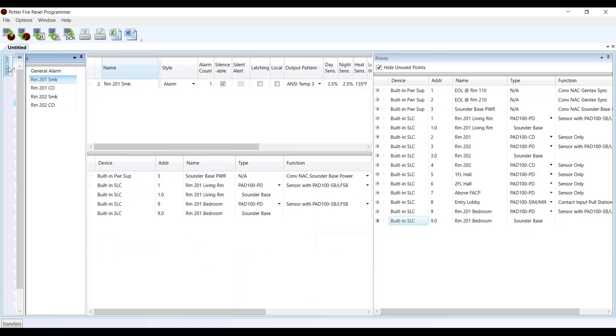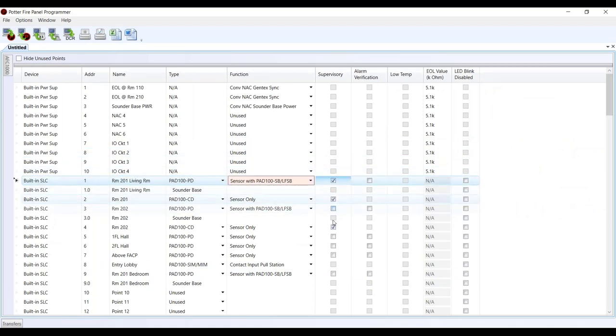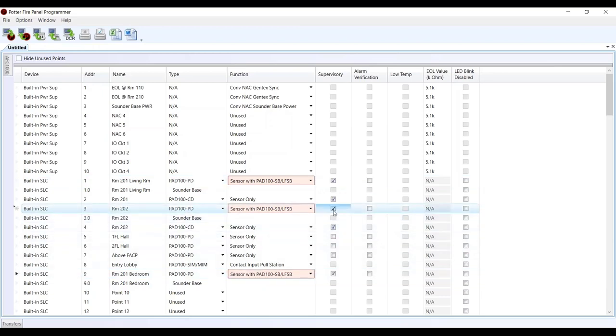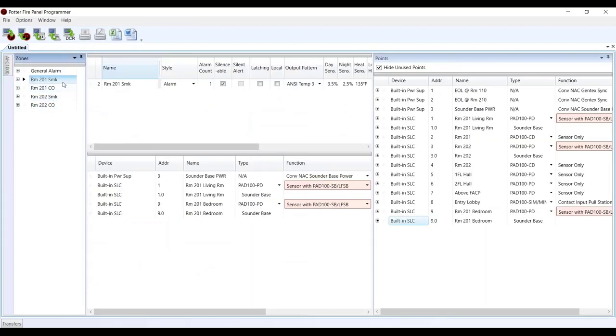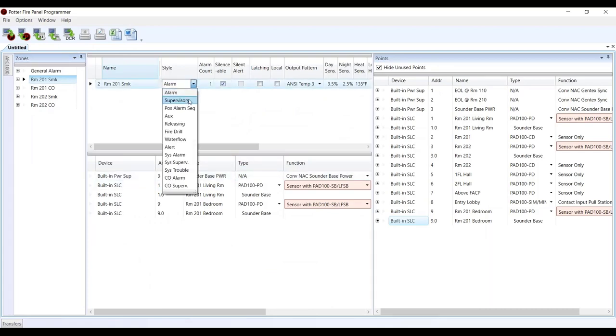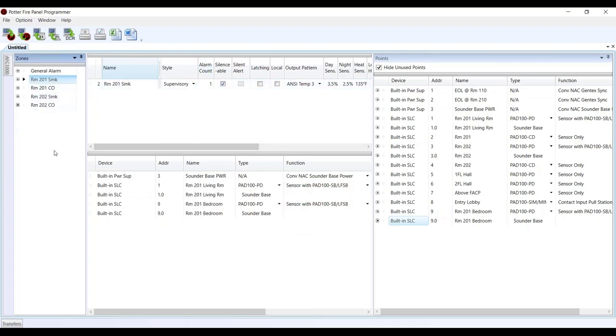Even if you wanted to do supervisory for the smoke detectors, nothing really changes except for the zone setting. Make those smoke detectors supervisory, go back to the room 201 zone — same exact concept, just make it a supervisory zone instead. Some places will do supervisory on individual room smoke, and then if you have two or three rooms in supervisory at one time it'll switch over to an alarm and activate full building evacuation.